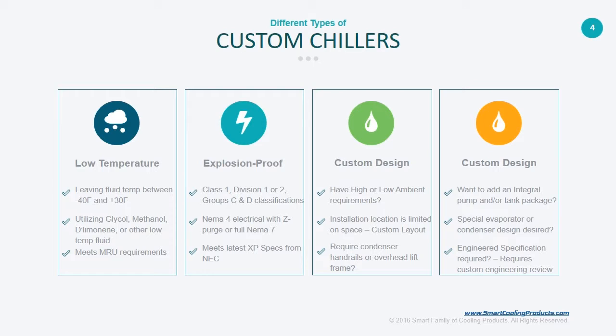The explosion-proof units, this is rather important because we've done everything from Class 1, Div 1 or 2. It states Groups C and D here. We've actually done Groups A and B as well. We like to make sure that our customers understand that the explosion-proof classifications do change occasionally. So if you've got either an older unit or you're looking at purchasing a newer one, make sure that you check the specs or have an engineer check the specs for you, to make sure that what you have or what you're planning on buying will be able to meet the new, up-to-date code. It's one of the things that we pride ourselves on. We try to stay up to date with that, and make sure that there haven't been any recent changes that could have been missed. We always want to make sure our customers are taken care of, and they are our number one priority.